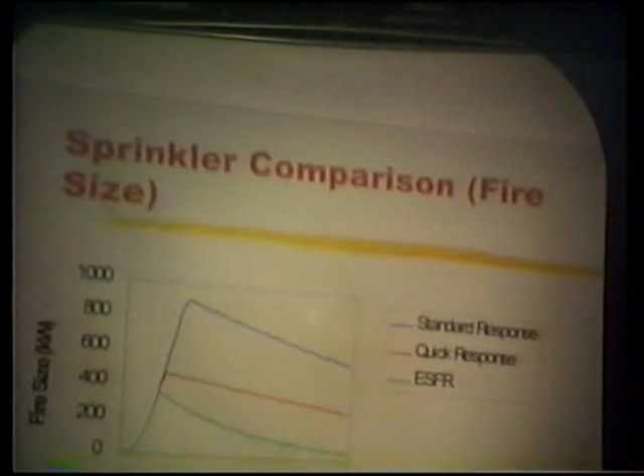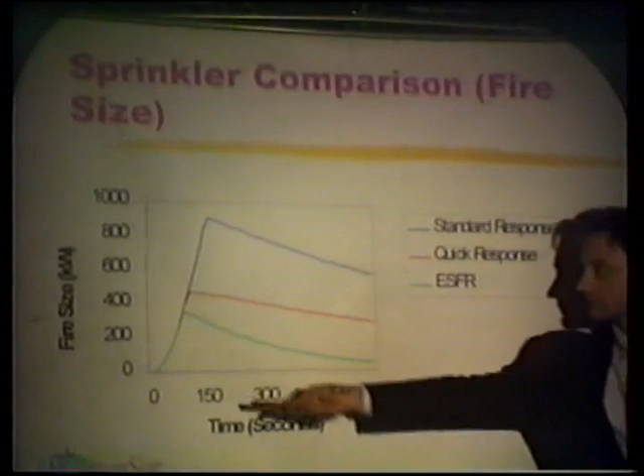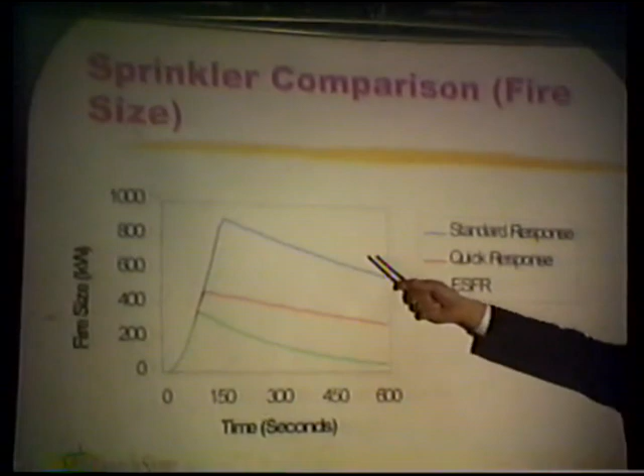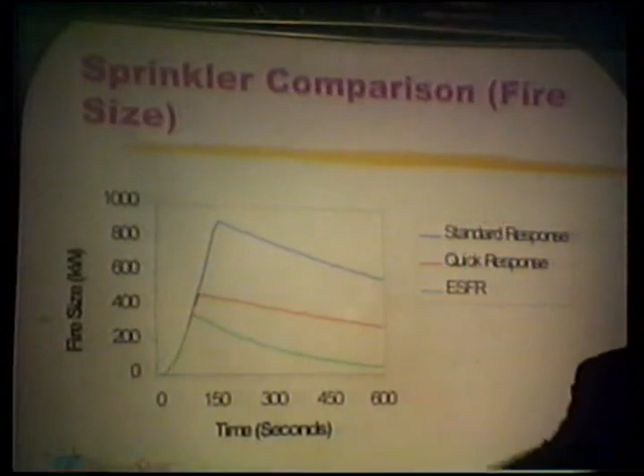Now, why would we want to know some of those things? Well, we could take different types of sprinklers and calculate the rate of heat release on the vertical axis, with time along the horizontal axis. Here we did a mathematical computation, given a building, I forgot what the height of it was, but it's all the same height. But notice the difference, and you would know this intuitively, between the response fire size with standard sprinklers, quick response, and ESFR. Now, if we're purists with ESFR, we believe it will actually put out the fire, with the heat release going down. However, the point being made here is that we can approximate the fire size when the sprinklers go off.